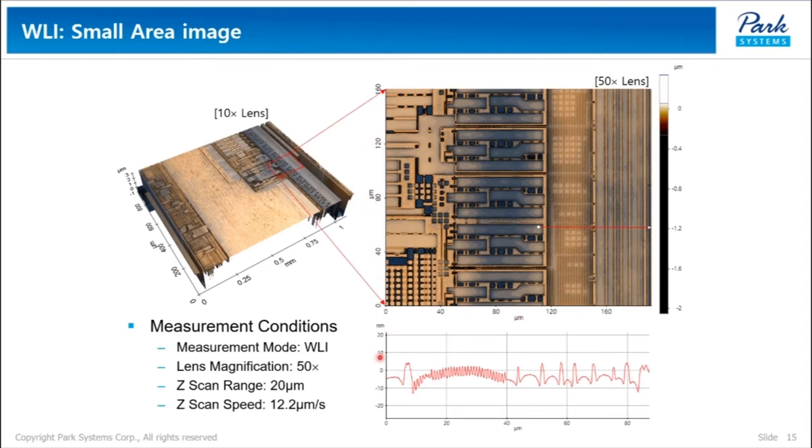In this result, a 10 nanometer step-height sample with a feature size around 1 micrometer was successfully measured. In conclusion, metrology capability was approved by the results. Remaining work is application function testing like area stitching and defect review, and these are currently being tested.